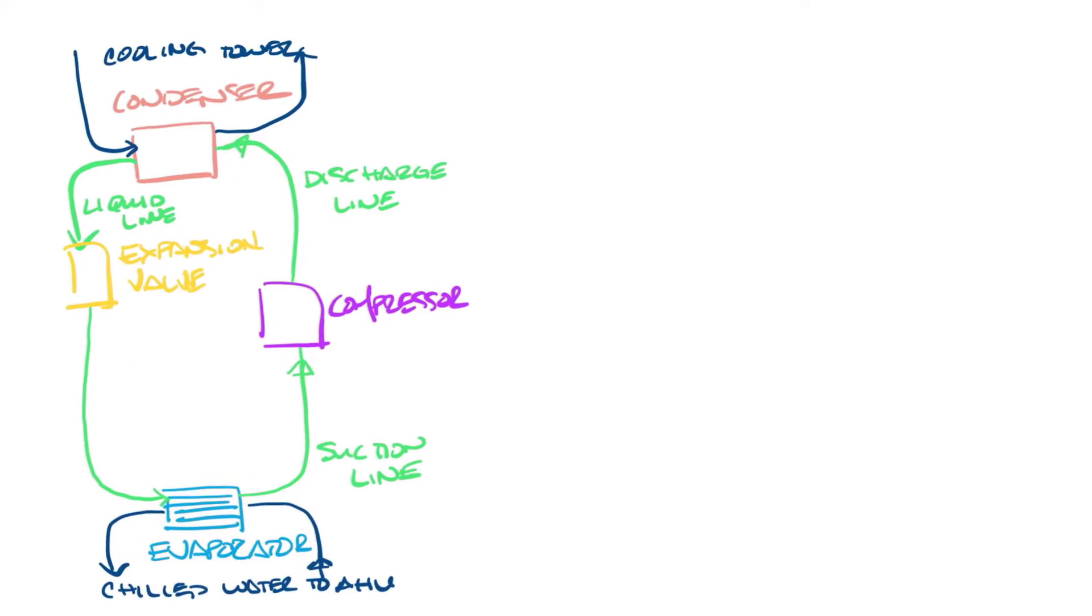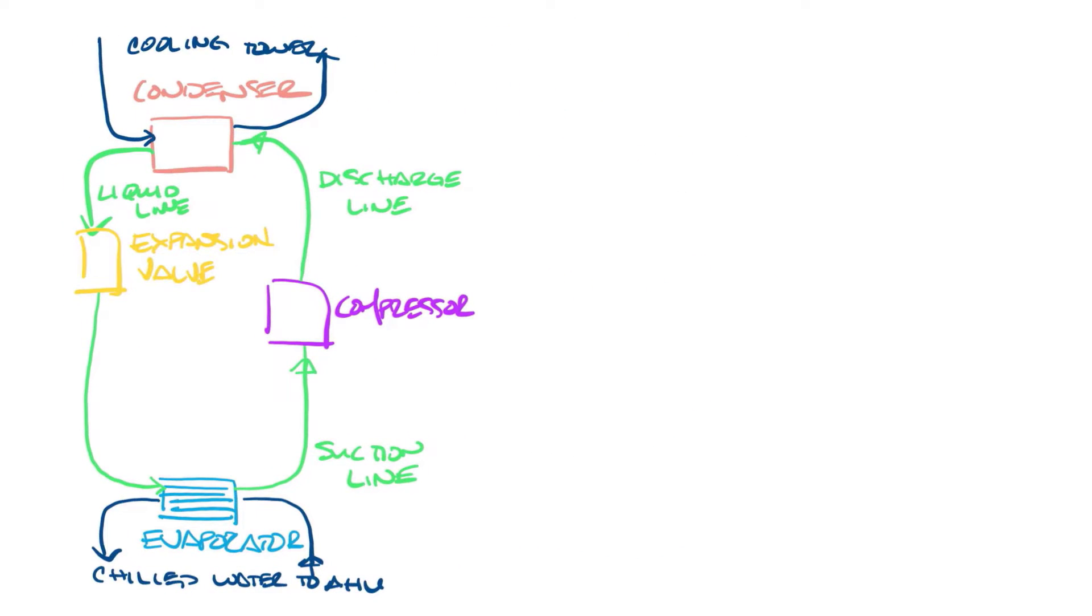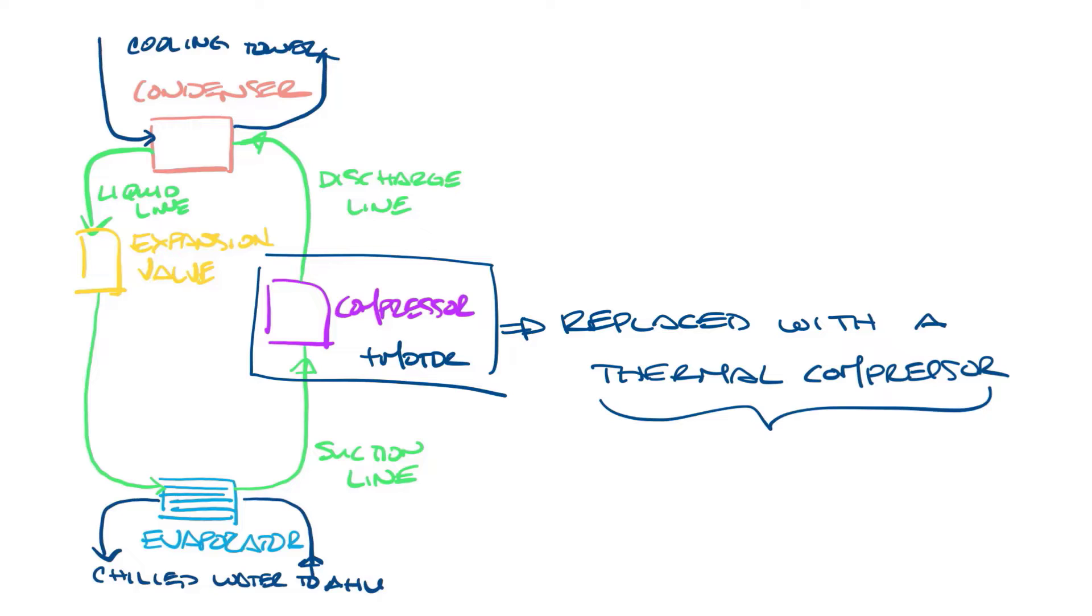Now let's bring up part of the picture from a couple videos back that shows the basic chiller components. In an absorption chiller, the compressor and its prime mover, the motor, are replaced by a thermal compressor system consisting of an absorber, a pump, and a generator.